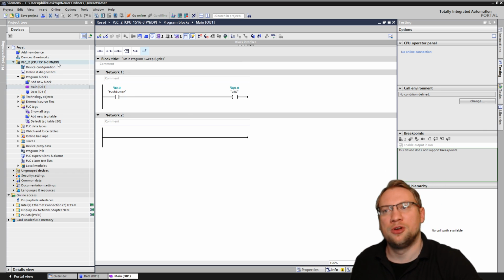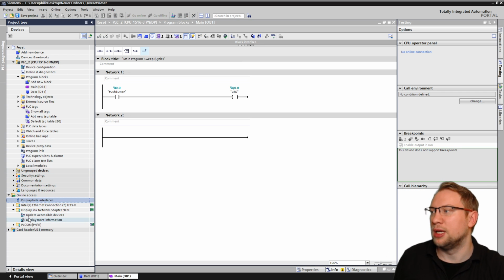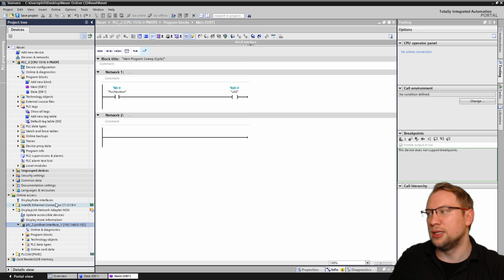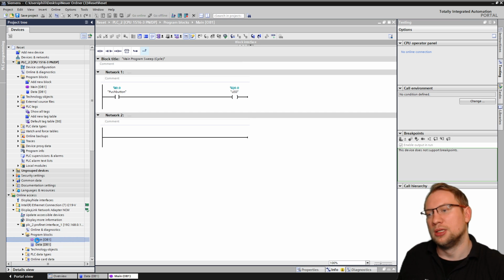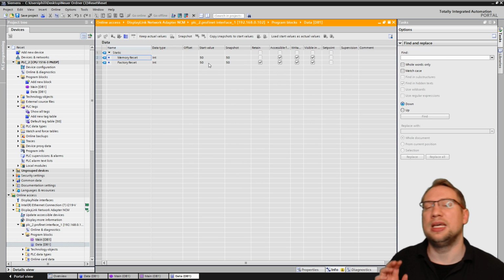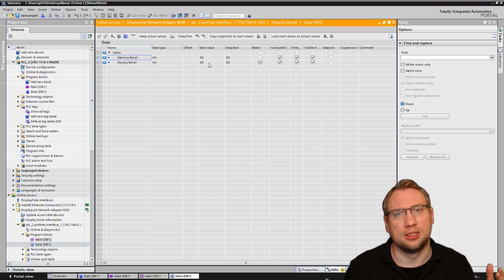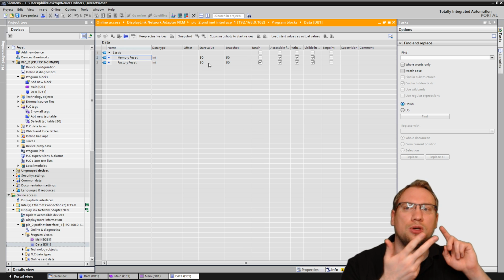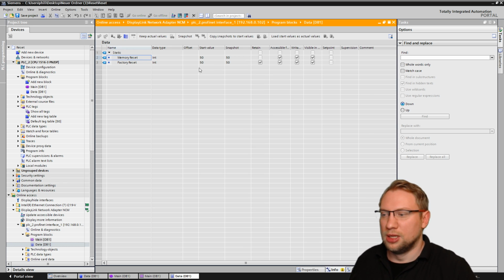Still with a memory reset, if I now go here on the left side in my network card and in the diagnostics, let's see, the PLC is there. It still has a name, it has the correct IP address, it still has a program online, and it also still has the variables. So all our data is not lost, our program is not lost, just the variables, they are reset, right? It's a memory reset. All your counters will be reset, all your timers, all your variables that you have, all your connections, stuff like this is all reset now.